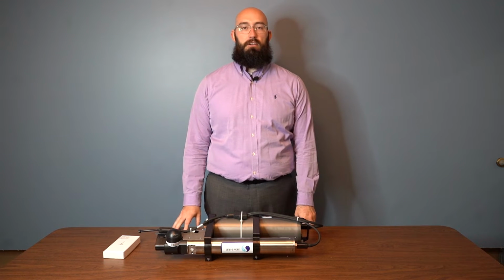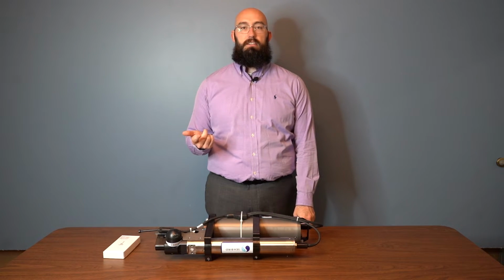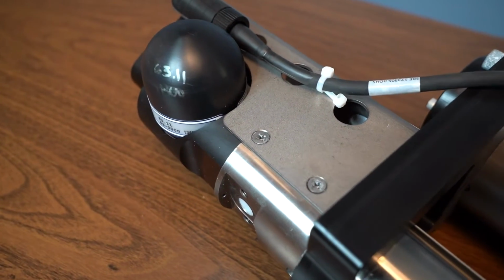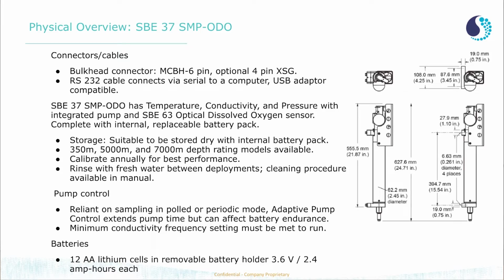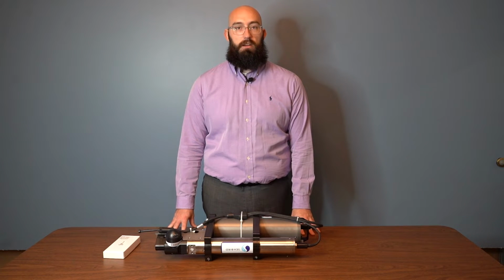The 37 SMP ODO comes outfitted with a conductivity, pressure, temperature, and 63 oxygen sensor. There's also an integrated pump, which is controlled via the adaptive pump control setting, your minimum conductivity frequency setting, and the polled or periodic mode. The system also has a replaceable battery pack, which is complete with 12 AA lithium cells in a removable battery holder. You can find more information about those specs in the manual. The Deep SeapHOx generally has a 5,000, 7,000, or 350 meter depth rating. We recommend that all sensors are calibrated within 1 year of their purchase or previous service.